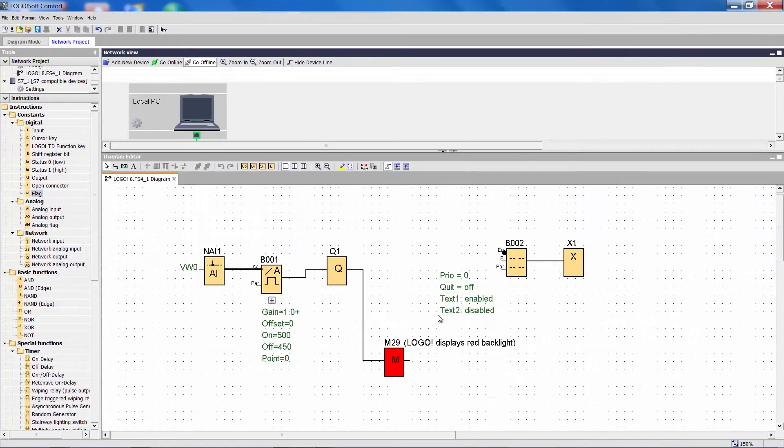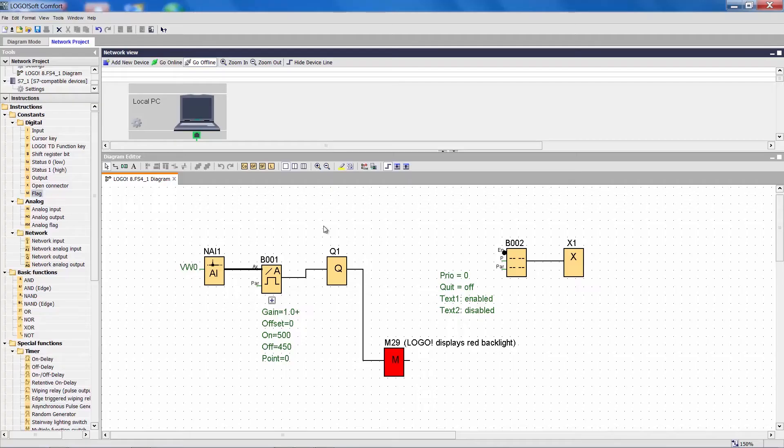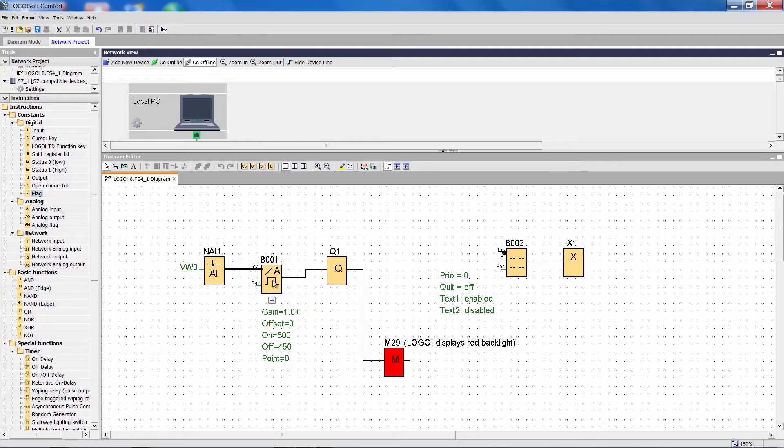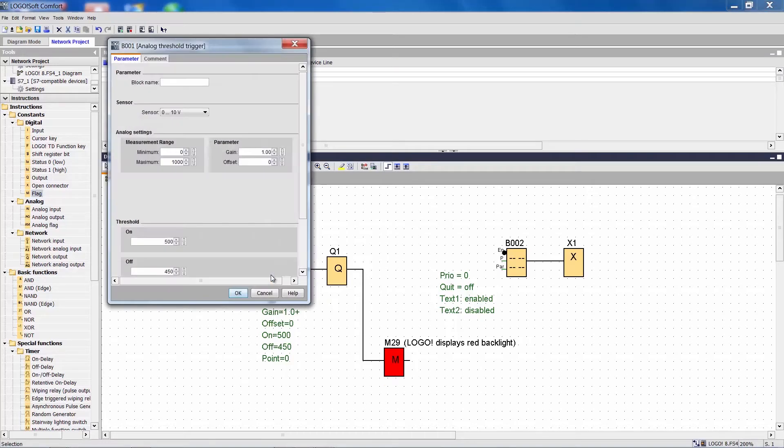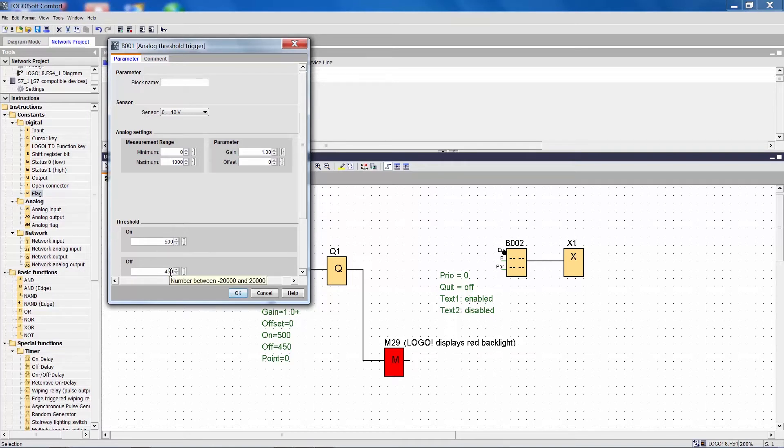The actual Logo program consists of just a few function blocks. We use the analog network input to evaluate the value of the SIMATIC device. A threshold switch is configured to activate the output as soon as the value exceeds 500 and to deactivate it at 450.